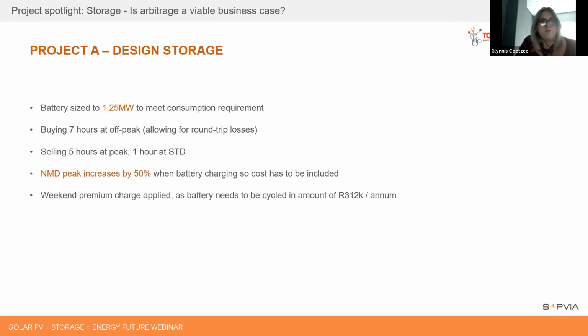So we sized the battery to a 1.2 megawatt size battery to meet the consumption requirement. We came out at a scenario where we'd be buying 7 hours off peak, allowing for round trip losses, at the minimum amount of cost, and then selling back to the plant at peak for the 5 hours of peak. If you remember the wheel, it's those 5 red hours and 1 hour standard.